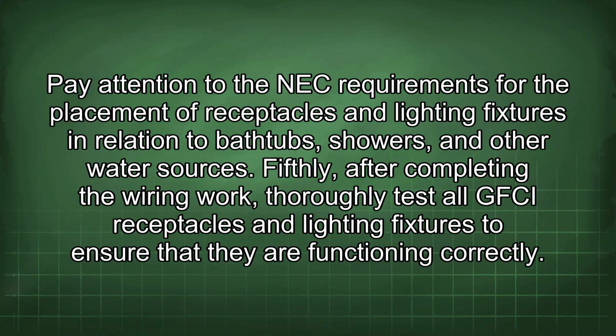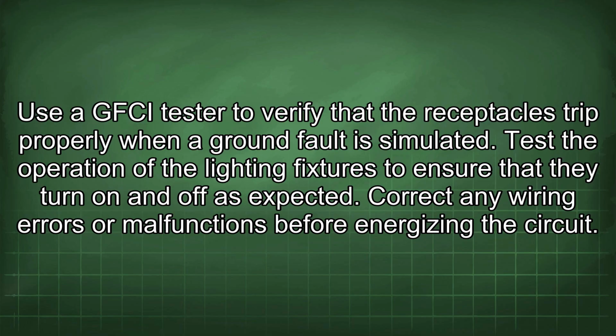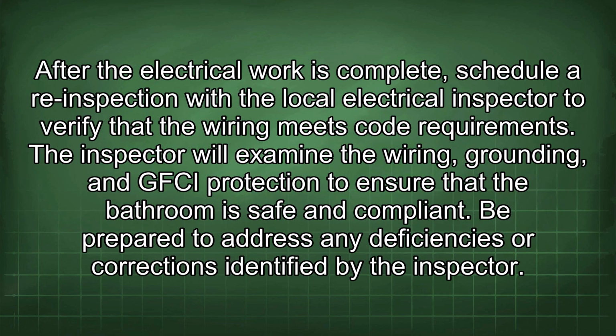they are functioning correctly. Use a GFCI tester to verify that the receptacles trip properly when a ground fault is simulated. Test the operation of the lighting fixtures to ensure that they turn on and off as expected. Correct any wiring errors or malfunctions before energizing the circuit. After the electrical work is complete, schedule a re-inspection with the local electrical inspector to verify that the wiring meets code requirements. The inspector will examine the wiring, grounding, and GFCI protection to ensure that the bathroom is safe and compliant. Be prepared to address any deficiencies or corrections identified by the inspector.